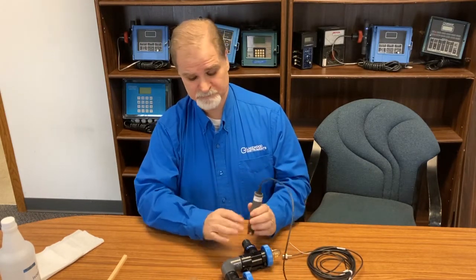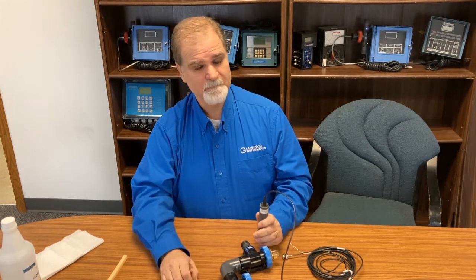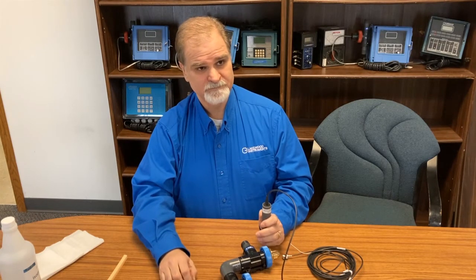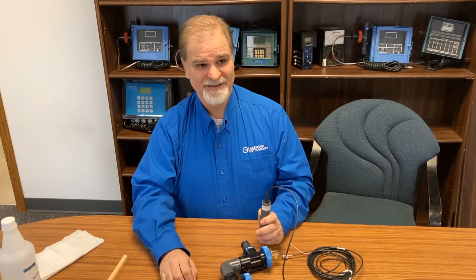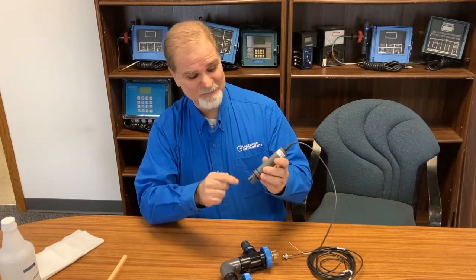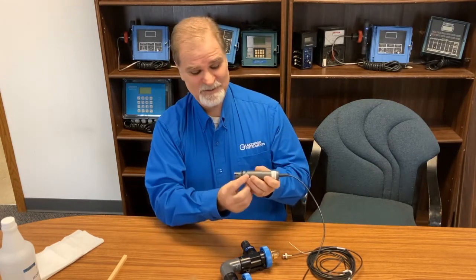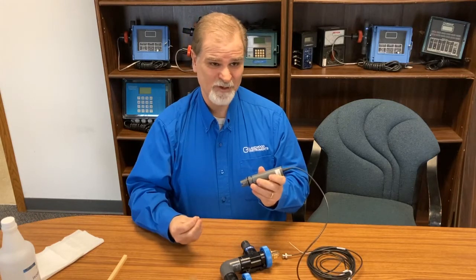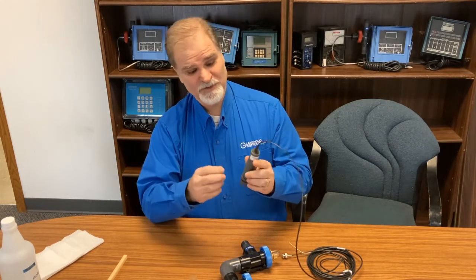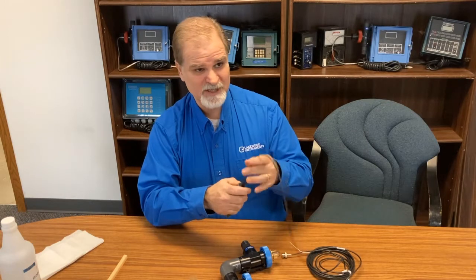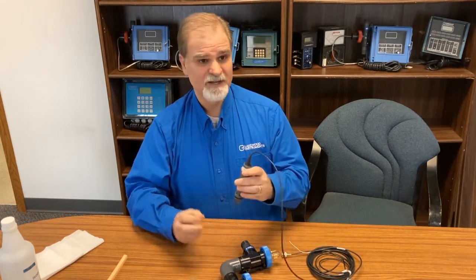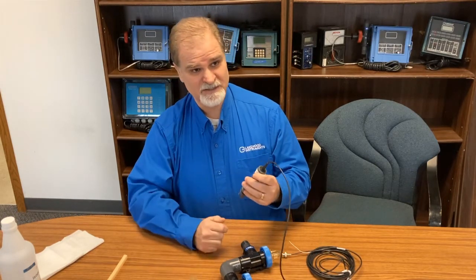And for people maybe in the more northern climates who may shut down a cooling tower for the winter, what kind of things do they have to worry about? Well, the pH and ORP sensors are made of glass, which means that they can freeze and break in the wintertime. So if you're going to shut down the system during the winter months, you should pull the sensor and bring it indoors to keep it from freezing.